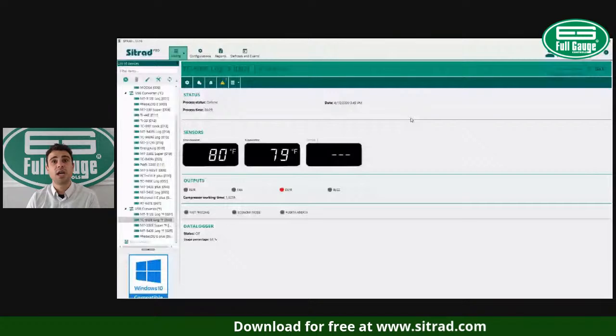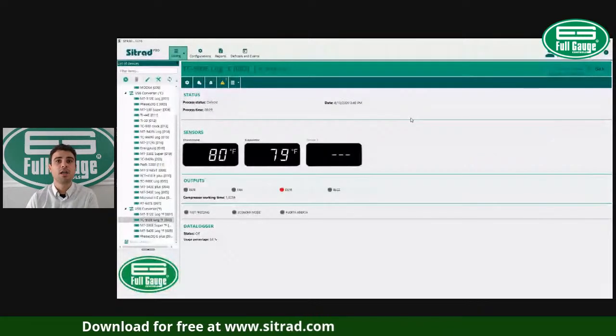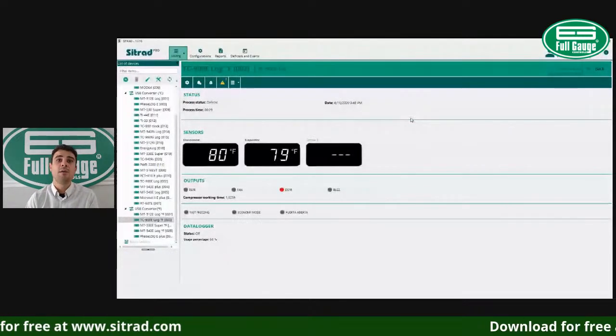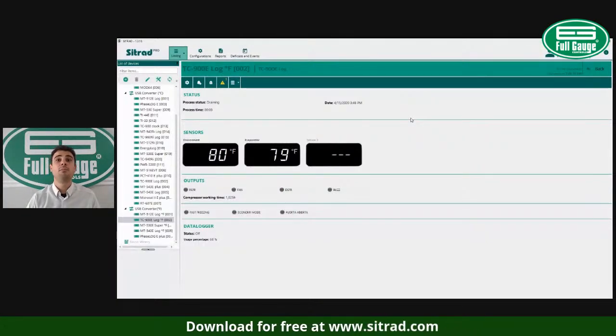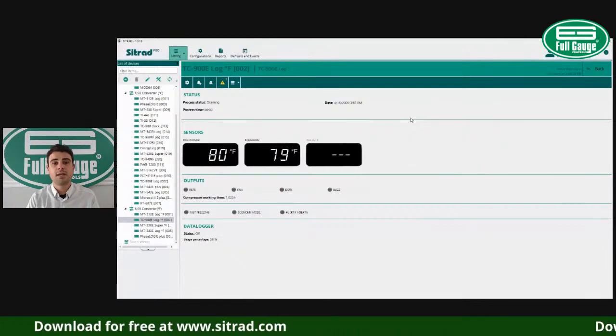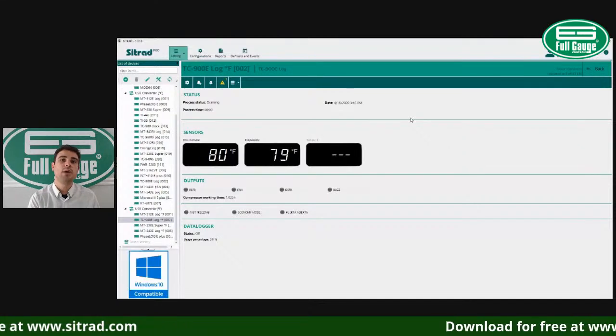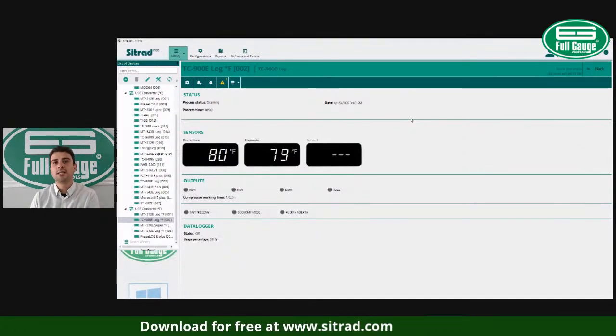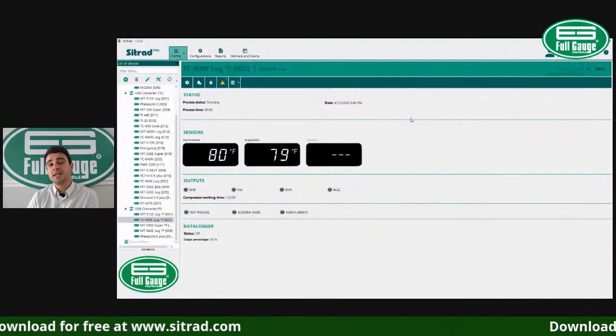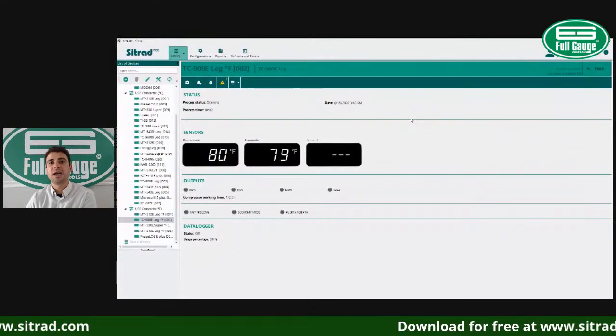So you might have to check why that happened, or if that is constantly happening, maybe your defrost termination temperature is too high, or maybe there are other things to look at. But that's why we had the alarm, because this controller wants to terminate the defrost always based on the coil temperature. And in this case, unfortunately, it terminated by time.